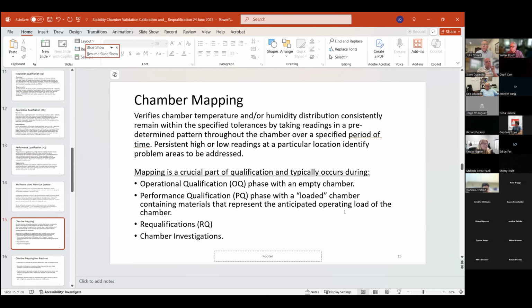Okay, let's move on to chamber mapping. Mapping verifies that chamber temperature and/or humidity distribution consistently remain within the specified tolerances by taking readings in a predetermined pattern throughout the chamber over a specified period of time. Persistent high or low readings at a particular location identify problem areas to be addressed.